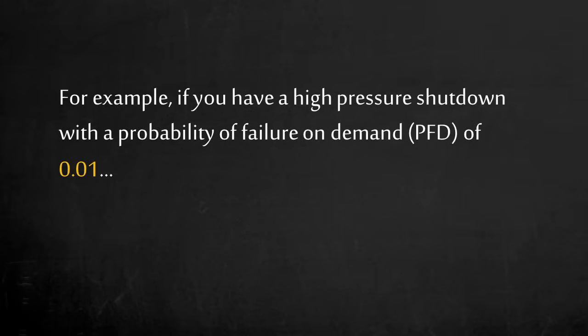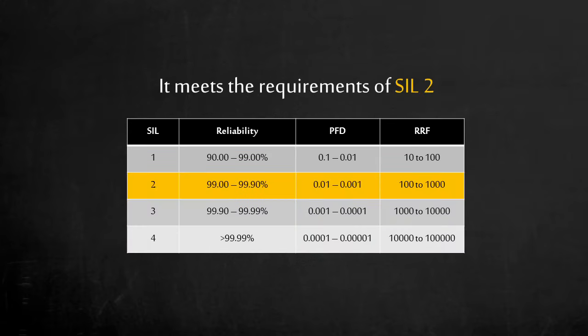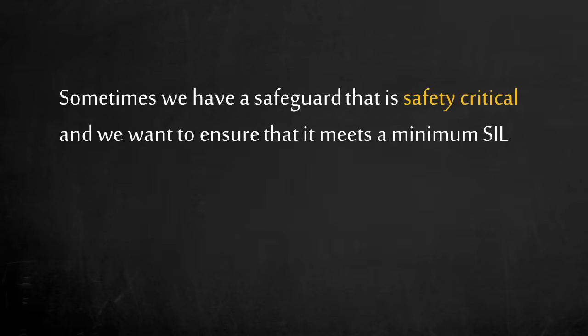For example, let's say we have a high-pressure shutdown that has a probability of failure on demand of 0.01, or in other words, 1% chance of failure on demand. The high-pressure shutdown meets the requirements of SIL 2. Safety functions that meet this safety integrity level are capable of achieving a risk reduction factor of 100 to 1000. This is a key concept here. Depending on the specific process, other protection layers in place, and the tolerable frequency of a consequence, an automated function may be safety critical and need to meet a minimum safety integrity level.